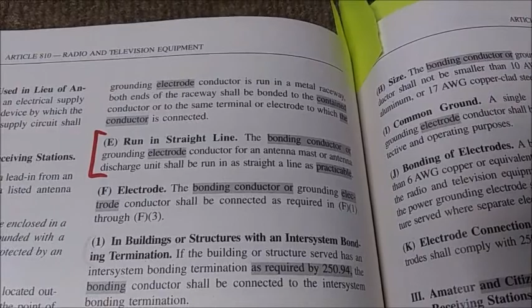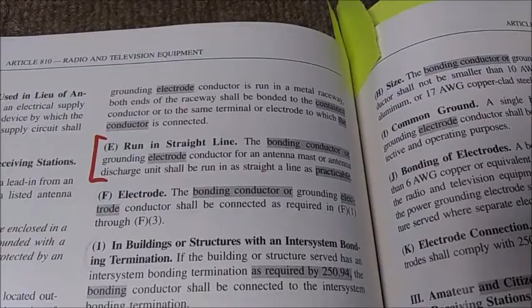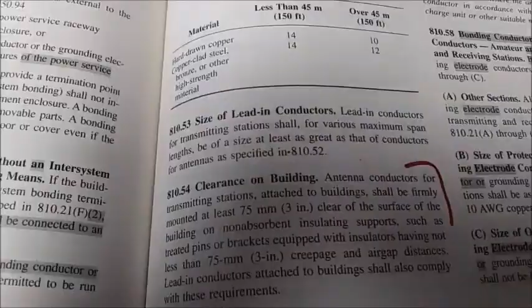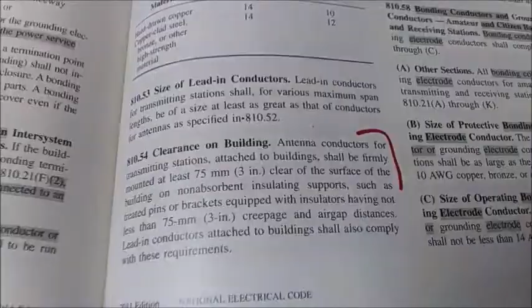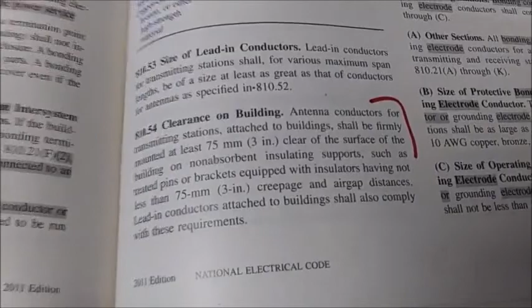The bonding conductor or grounding electrode conductor for an antenna mast shall be run in as straight a line as practical. Bending a ground wire is a disaster because that causes crowding of the field lines in the bend and causes an increase in inductance. And when a transient hits that, it sees it as an RF choke and creates a high voltage. Here's another part of the code that's violated.